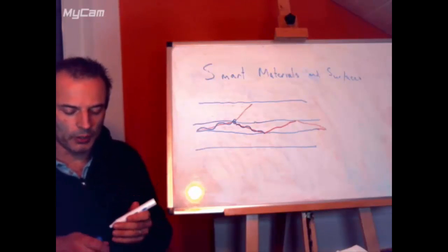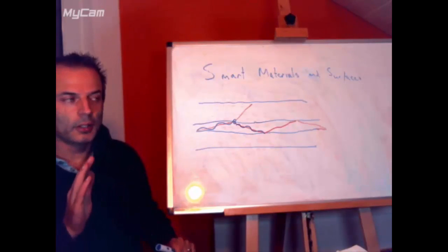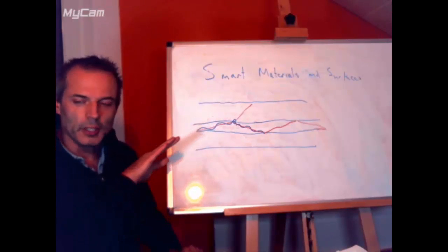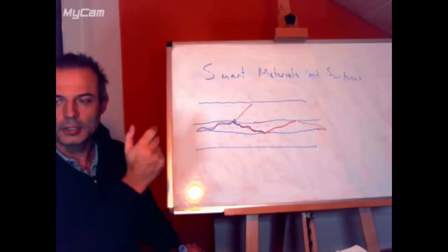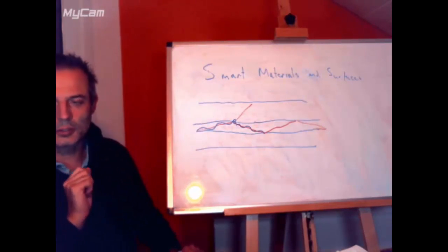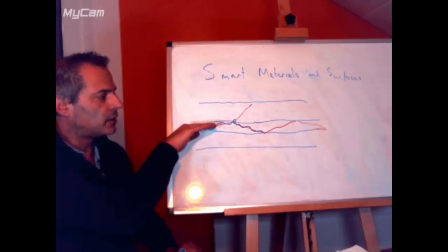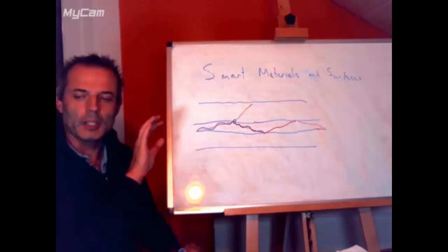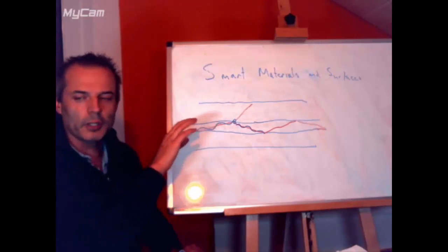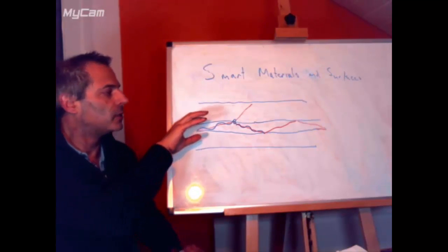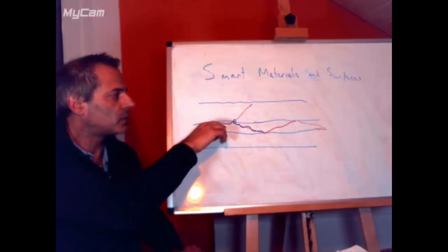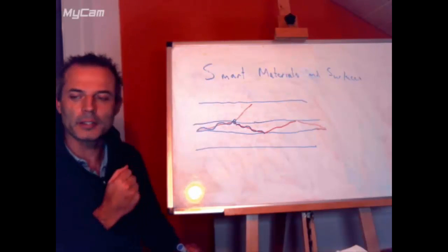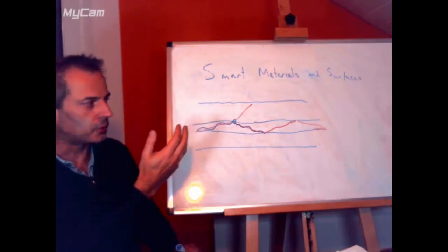And that is how our ATR infrared attachment works. It bounces the infrared light on the inside of a piece of zinc selenide. It can't be glass because glass is not transparent in infrared. And the infrared beam looks out a little bit. It's a fraction of a wavelength, so it's not very far. It looks out a little bit into the outside world while it is doing effectively the maths of working out whether it should be bouncing off or not.